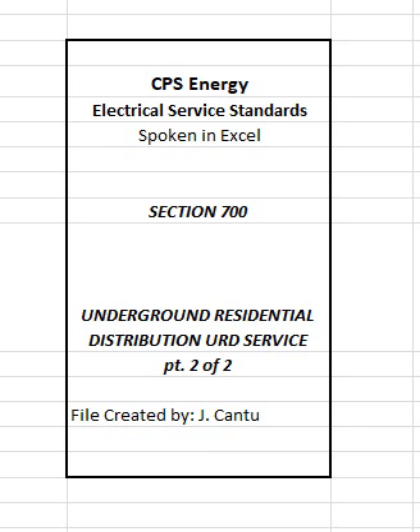704 Service conduit routing. Underground service lateral conduits shall be totally outside the building and located to provide the shortest practical distance between the CPS Energy transformer or secondary enclosure and the meter loop. Service lateral conduits will normally be located so they will contact the side of the building that the CPS Energy customer service representative designates. Service laterals will normally run parallel to side property lines.